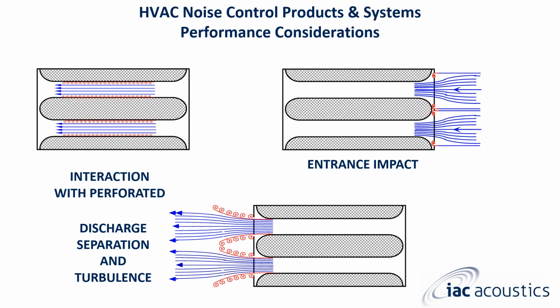At the top right, you see some self noise that can be generated right at the entrance of the silencer. With our bell mouth entrance and exit, though, our silencers act better. It helps to separate the air. At the bottom left, you can see the discharge separation and turbulence is very, very minimal. Some noise can be generated at the discharge of a silencer, but again, with the bell mouth entrance and exit, air comes in equally and exits equally.